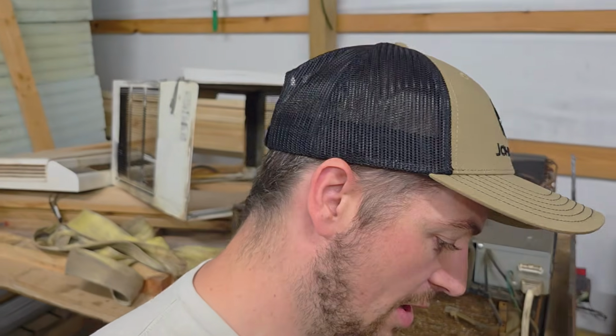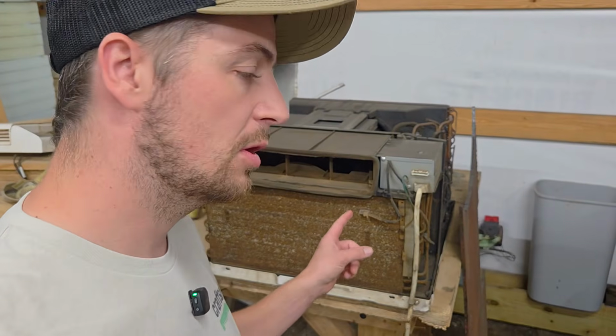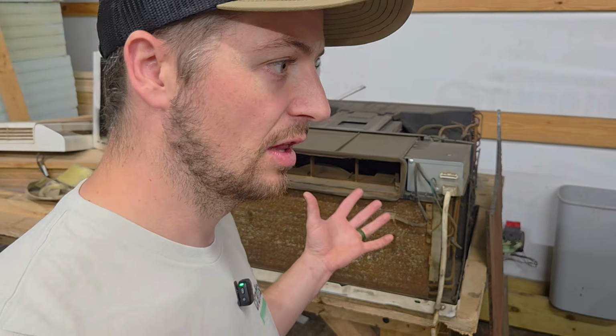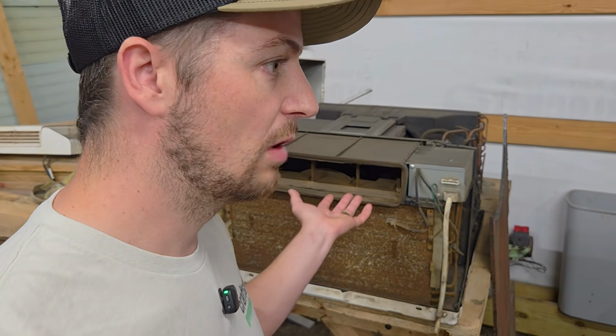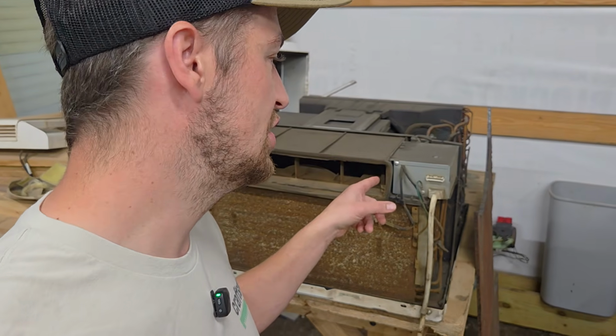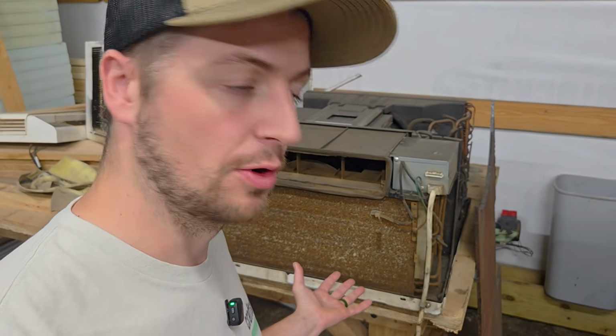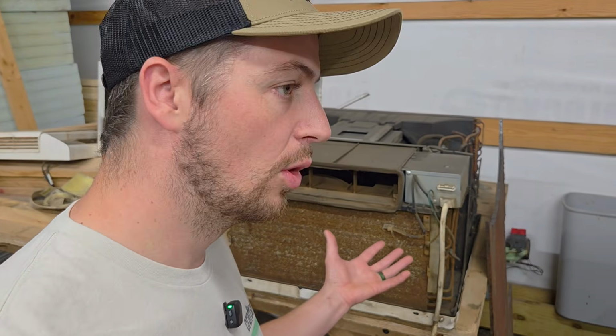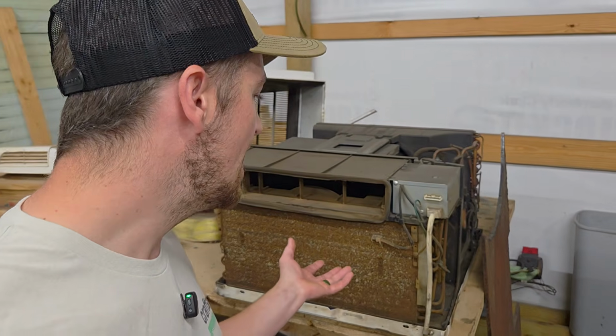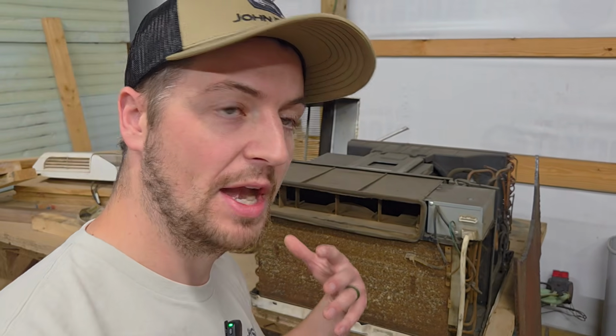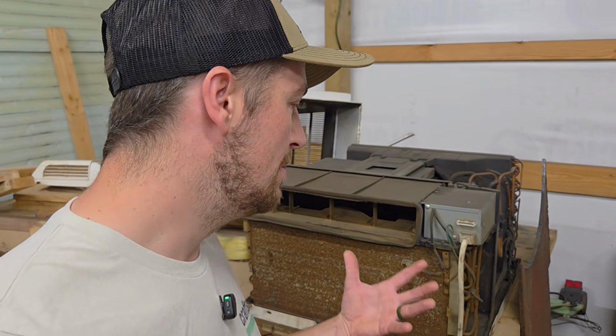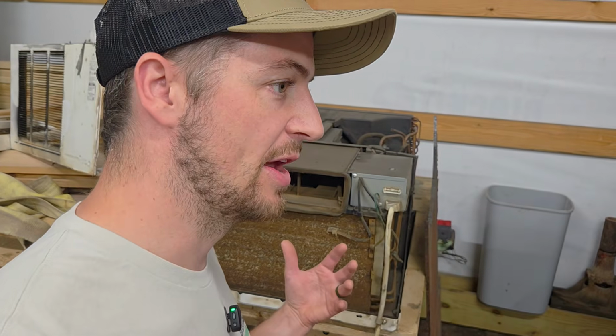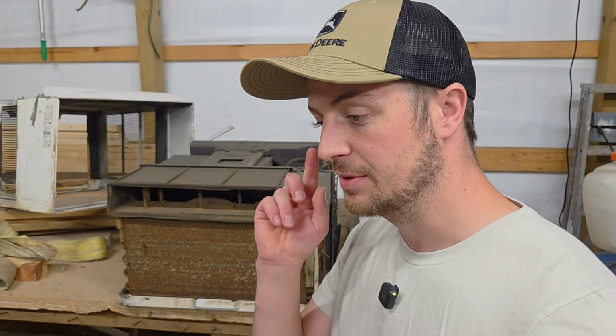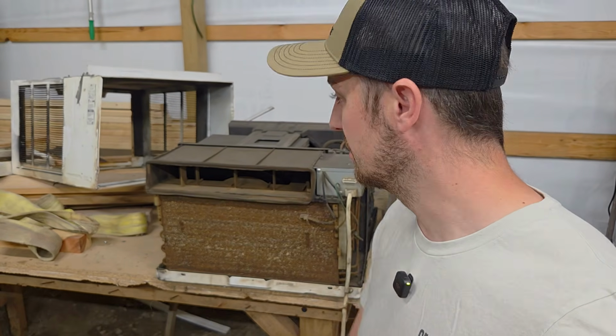Now, the question that I have though is, if I don't do that, and if I want to build a water-to-water heat pump, will the window air conditioner work properly if the evaporator coil is only like 45 degrees? Let's say when the glycol gets up to 50 degrees, I kick the air conditioner back on to bring that glycol back down to 45 degrees. I don't know if the evaporator coil and the design of the window air conditioner is designed to have the evaporator coil be a warmer temperature from that warm air in the house blowing by it. I don't know if it's going to mess up all the pressures and everything. That's why I'm not sure I want to go that route. And that's why I need your help to comment and let me know what you think. I just wanted to hop on and ask this because before I dive into this, I would like some feedback.